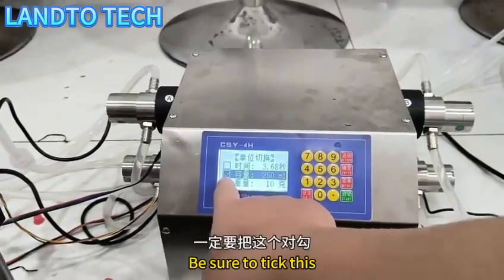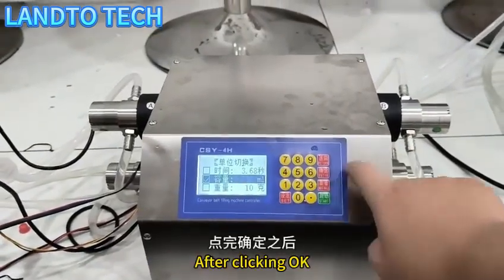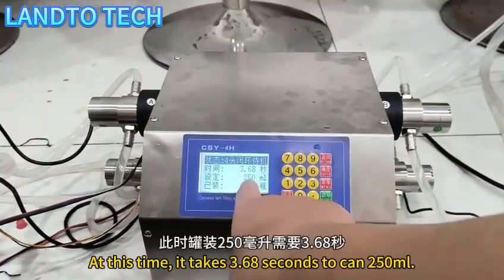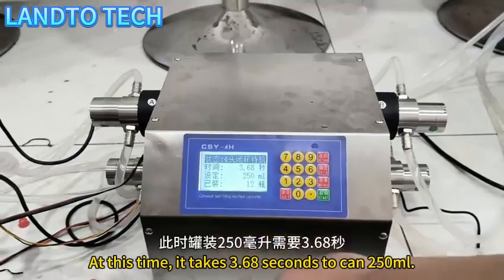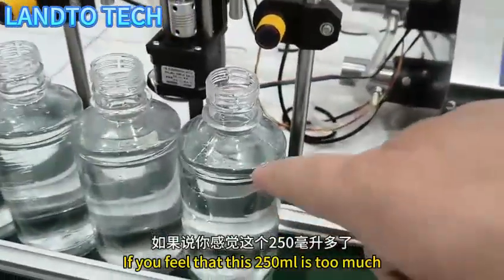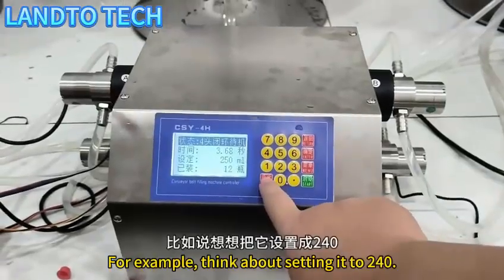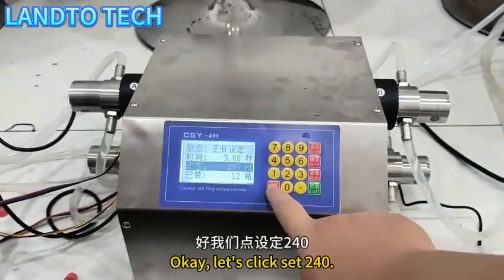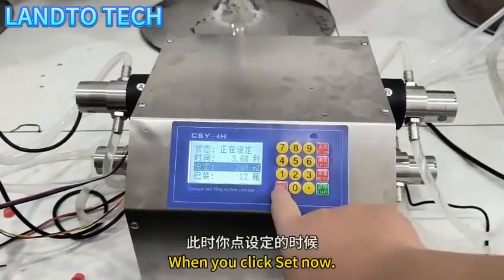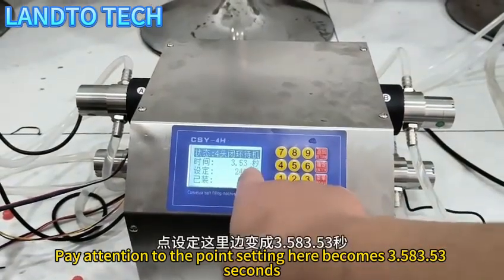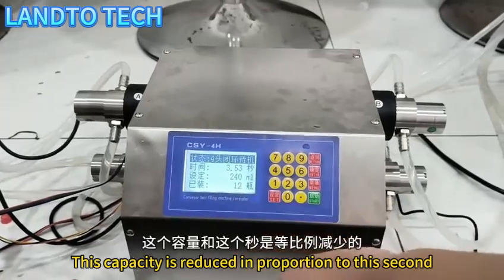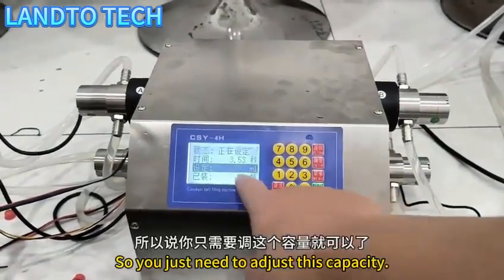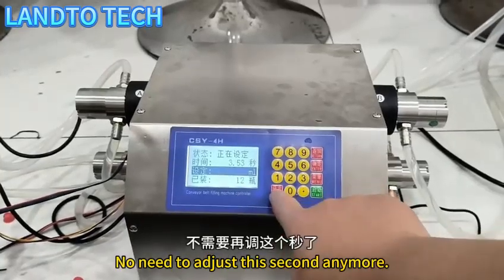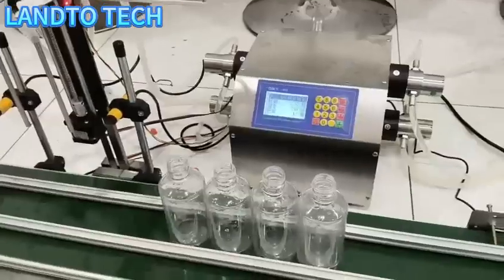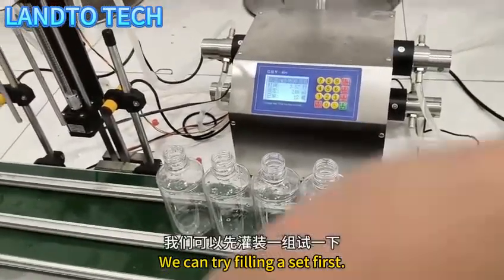Okay, let's make sure to put this check mark in front. After this click, we can click back. At this time, it takes 3.68 seconds to fill 250 milliliters. If you feel that 250 milliliters is too much, you can subtract a little. For example, set it to 240. Okay, let's click set 240. When you click set now, this second will change. Pay attention to the point setting here: it becomes 3.58 seconds. The seconds are reduced in proportion to this capacity. So you just need to adjust this capacity. No need to adjust the seconds anymore. At this point, our capacity is set.